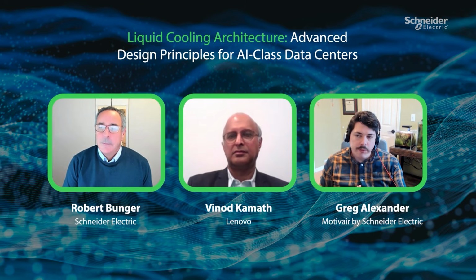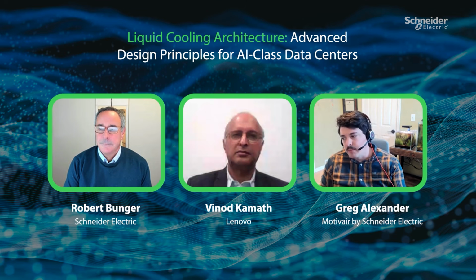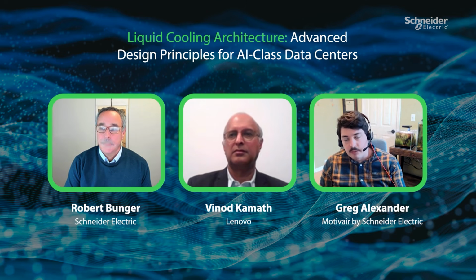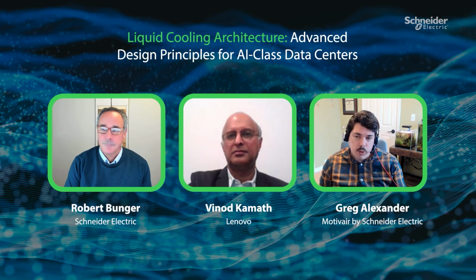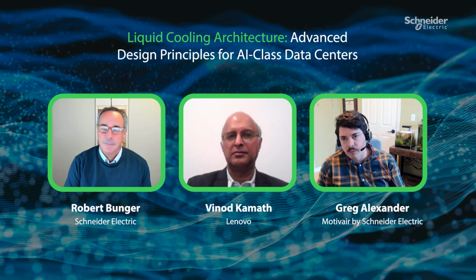ASHRAE's SSPC 127 is a special group devising the method of test for CDUs and other components within the data center. They've recently put out an addendum that qualifies that method of test to be set at 4 degrees ATD, between your incoming water to your ITE versus your cold water on the facility side. That's not to say all CDUs have to operate at 4, and they don't. There can be trade-offs either way depending on which direction you want to go. In general, as you shrink your ATD, that's going to affect your CDU designs for sure. But 4 would be typical based on ASHRAE's point of view.